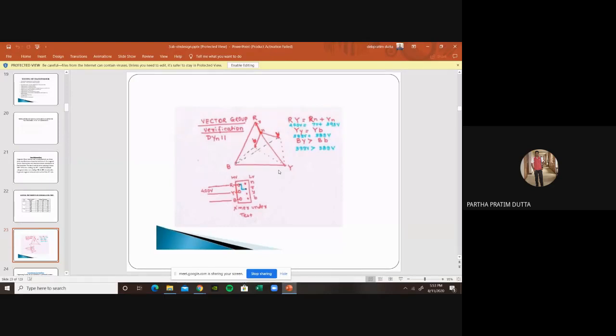In the case of the 33 by 11 kV power transformer, on the 11 kV side we usually use the same configuration and vector group, as we experience that earth faults are frequent in the 11 kV system, but not frequent in 33 kV or above systems. So to detect earth faults, our neutral point is very much required. When I discuss the protection system, you will see. That's why we use DYN11. In that case, we usually do vector group verification on these transformers.